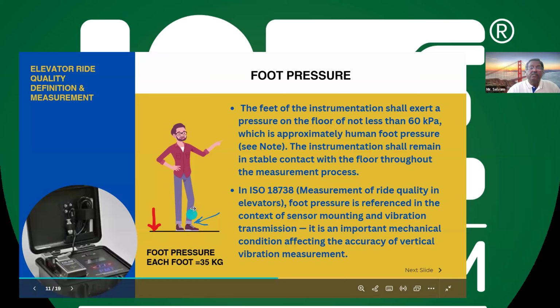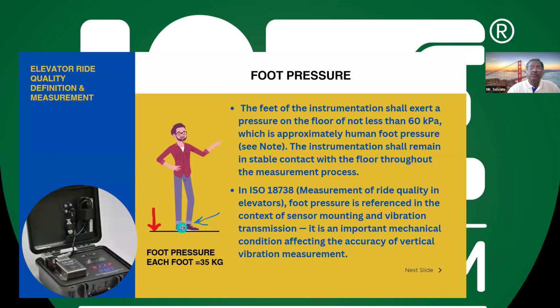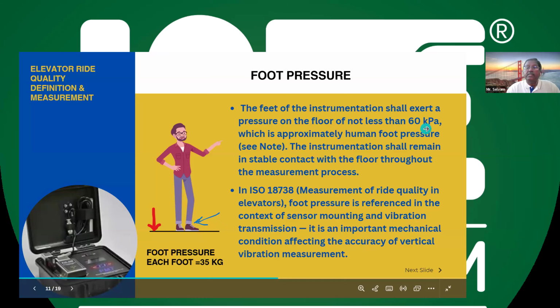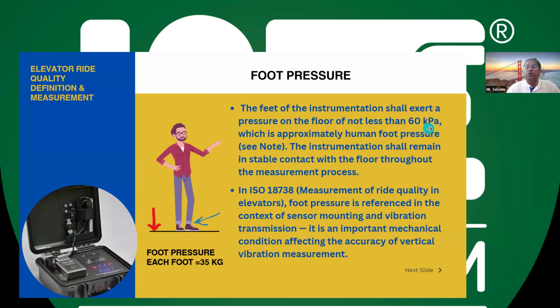Here, the 68 kg body is applied over some 200 square centimeter area. That means, when you calculate pressure, it is force divided by area. So the standard says it has to be a minimum of 60 kilopascals. If it is this value, the accuracy of the sensing of the vibration will be correct. Otherwise, it may be misleading.